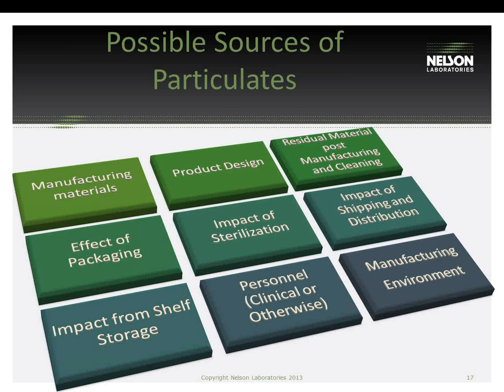Impact of sterilization hasn't been a big deal. It's of definite concern with regulatory. The FDA likes to see most products sterilized prior to testing. However, we usually don't find sterilization impacts particulate levels very much, although we have seen sometimes where shelf storage may be an issue, which we'll come to in a minute.